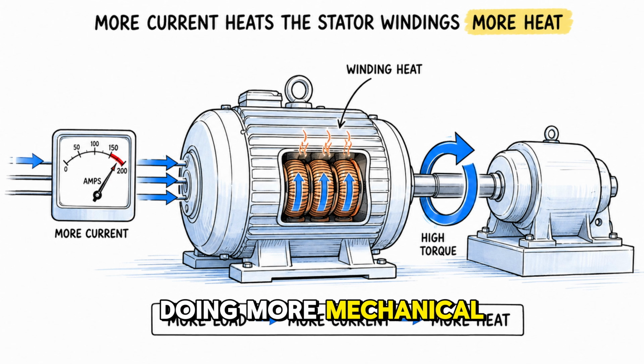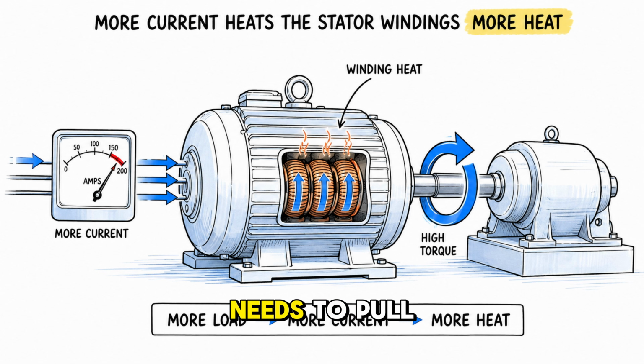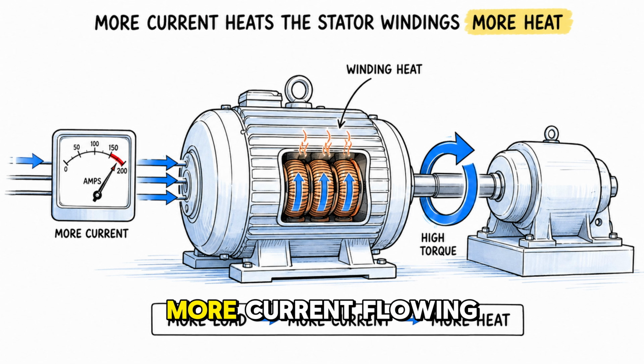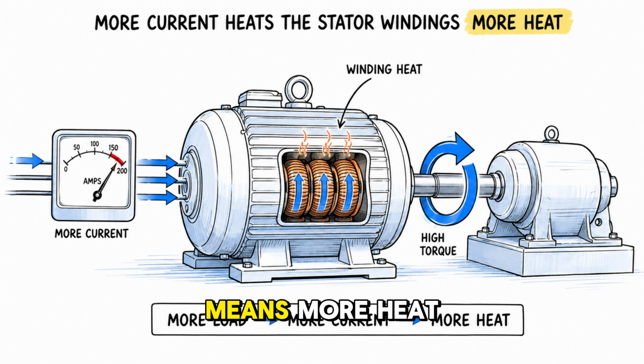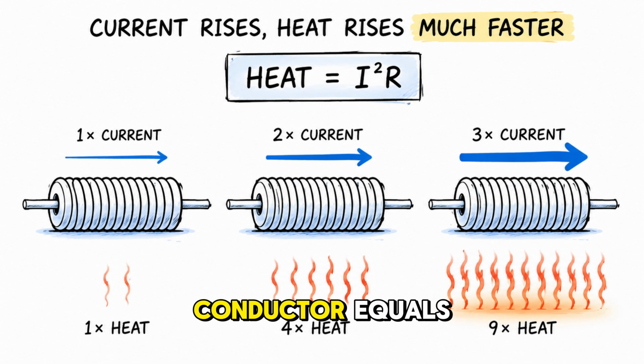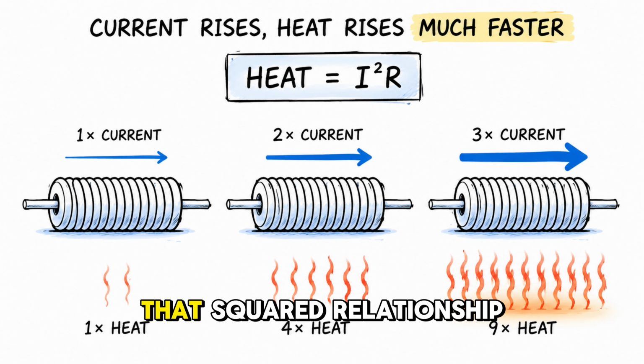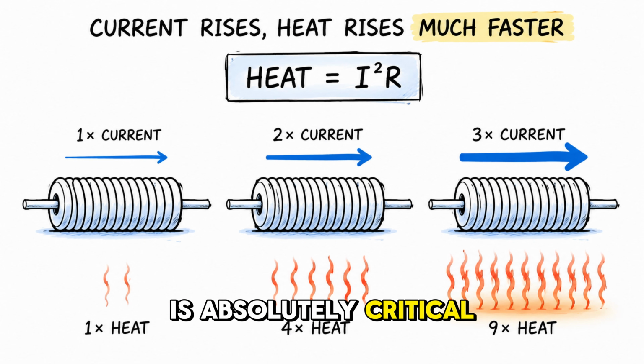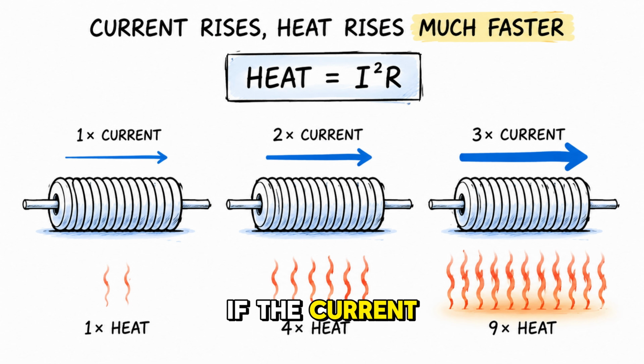The motor is doing more mechanical work, so it naturally needs to pull more current. More current flowing through the stator windings means more heat is produced by the winding resistance. Heat in a conductor equals current squared multiplied by resistance. That squared relationship is absolutely critical. If the current doubles, the heat quadruples. If the current triples, the heat increases 9 times.